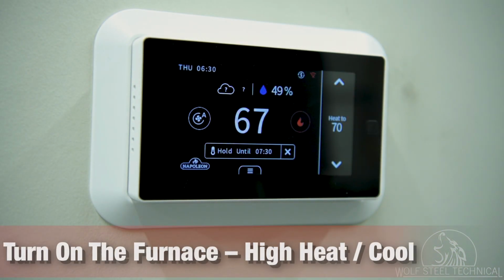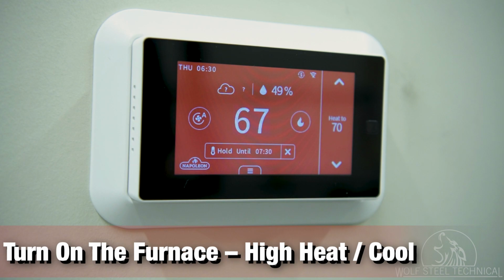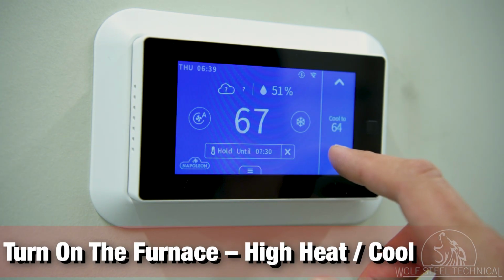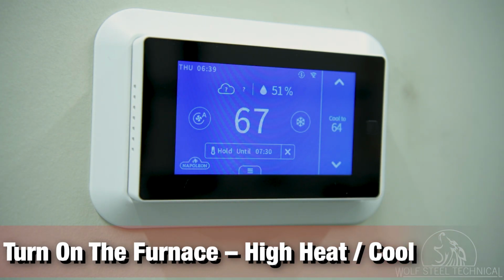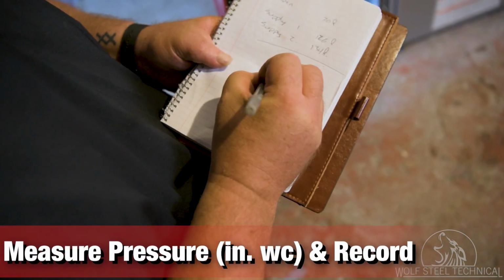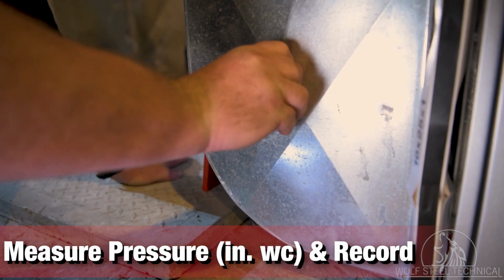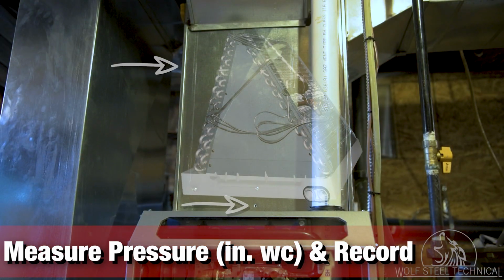Go to the thermostat and turn on the furnace to the mode with the highest fan speed. Allow it to run until high heat or high cool is initiated. Measure the pressure in inches of water column on the manometer and record the reading. If using a single port manometer, repeat the measurement at all locations in the return and supply air.